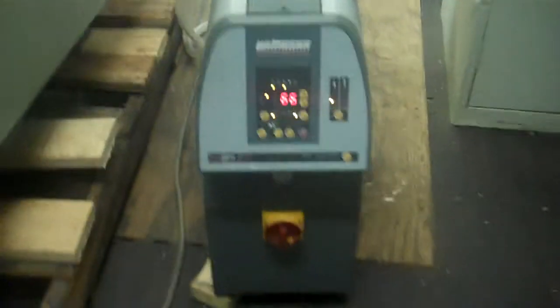Even. We're just starting to get a little bit below that -3 cutout. That's pretty good. That's behaving exactly as we would expect. Again, our temperature control unit here, which is leading to a little mini exchanger we had submerged in the tank, is only creating about 2 tons of heat. So we run this thing quite a bit.